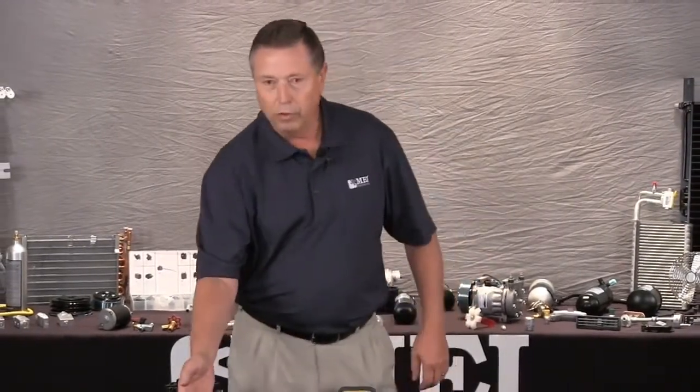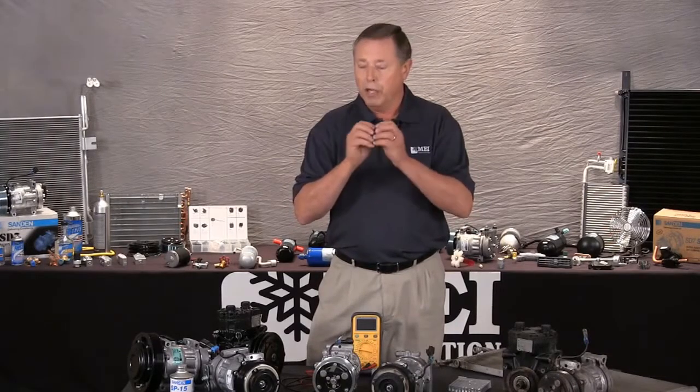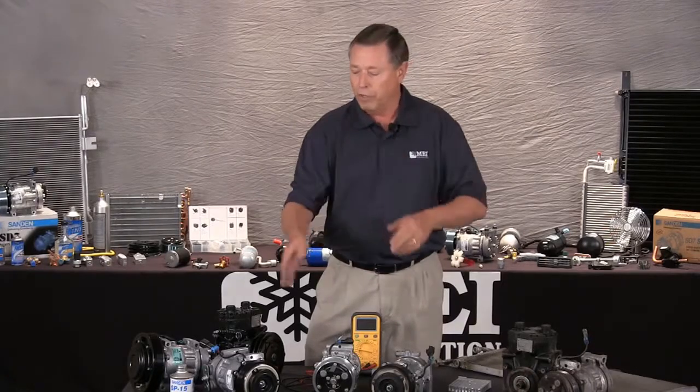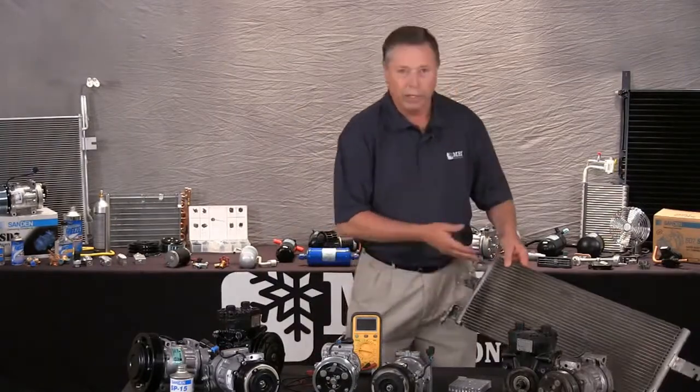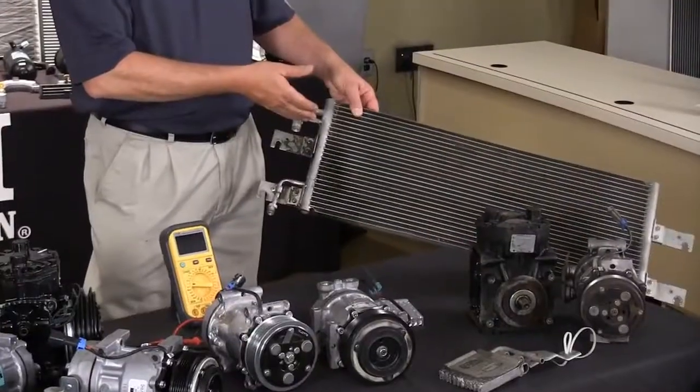And eventually, this little engine that we were talking about will run out of oil. As it starts to get low on oil, it's still running, it's still trying to do its job, but now these 7 pistons are rubbing with no lubrication and are going to be shedding metal. The Teflon rings on the pistons will start to shred. The wobble plate ball inside will start to tear up, and debris will come flying out of the discharge side of this compressor. And that will go directly piped into our condenser.